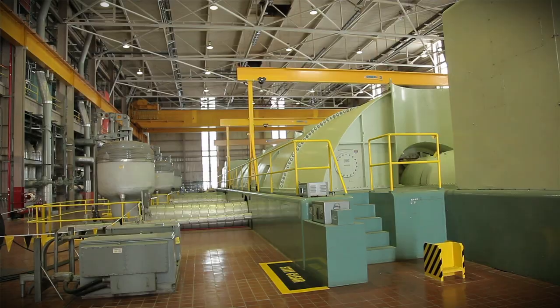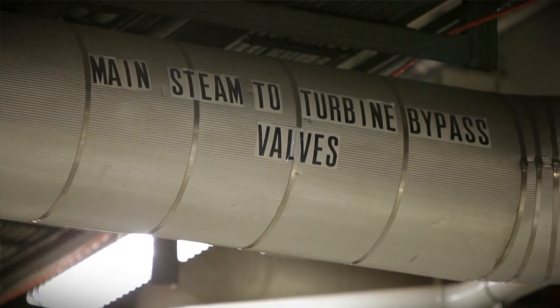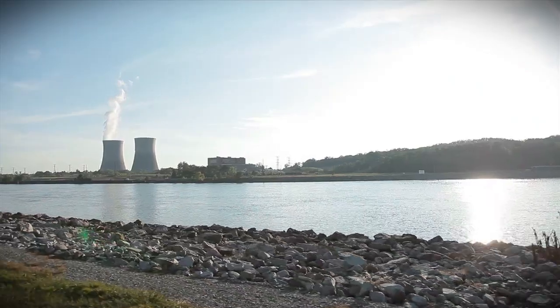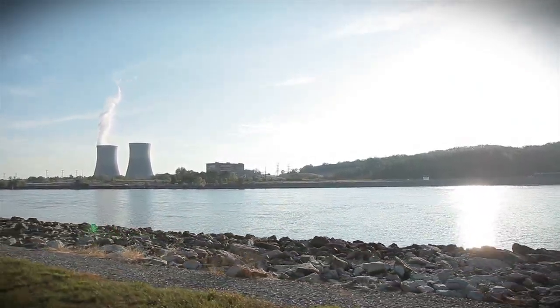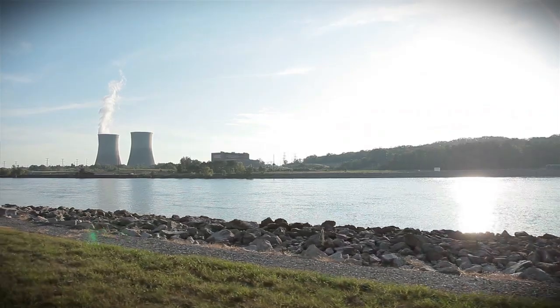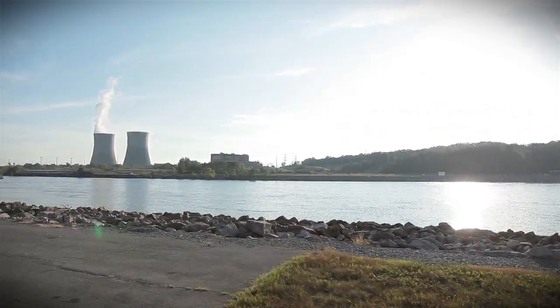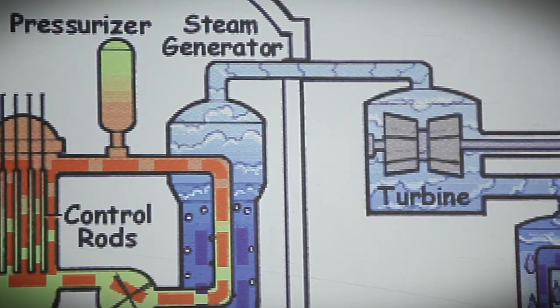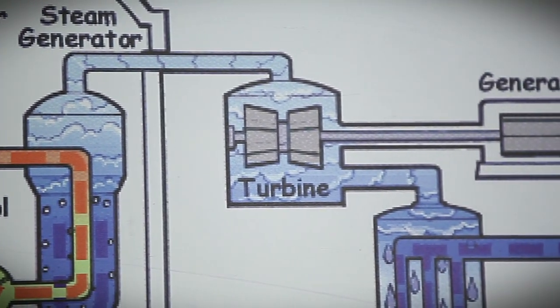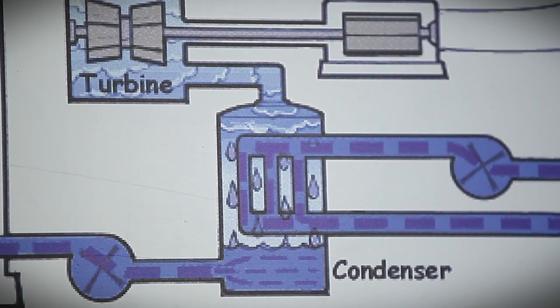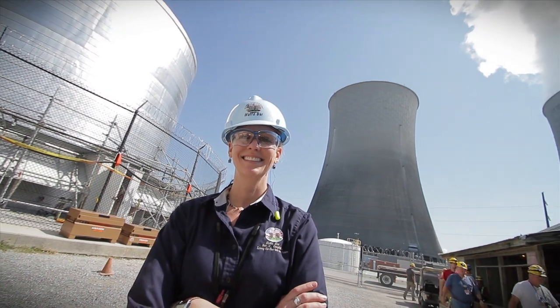In order to produce electricity, you've got to get the water so hot that it becomes super condensed steam. Eventually you have to cool it back down to bring it back up and create that electricity. So the cooling tower's job is providing the cooling medium to cool the exhaust from the main turbine. It allows us to take river water and use it to cool some of the equipment on the secondary side of the plant. It goes through the steam cycle, gets heated up, then passes through a condenser which removes the heat, and that's how you end up with vapor coming out of the cooling towers.